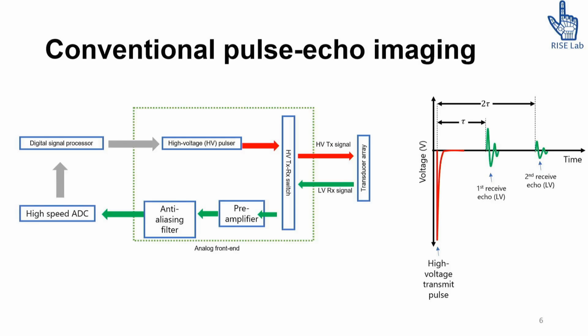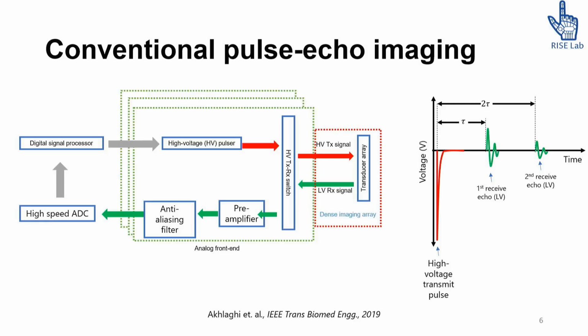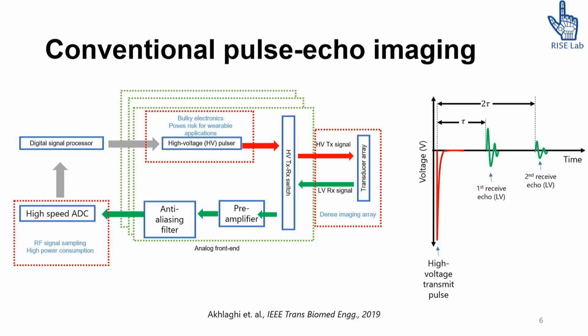And then, very importantly, what you're looking at is the transit time and the amplitude of the return signal in order to decipher how far the reflector is and how strong a reflector it is. So the temporal information is critical, as well as the amplitude information. The high-speed ADC plays a very critical role in this paradigm. And then typically you have a large array of these. One of the biggest challenges is that we are using a dense imaging array, which prevents miniaturization. We have high voltage electronics, which again prevents miniaturization. And we have RF sampling requirements, which doesn't allow us to break the low power limit.